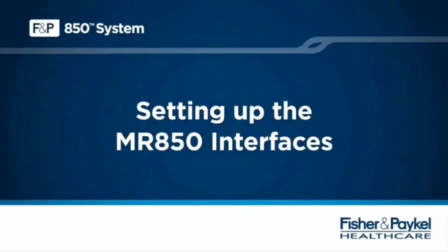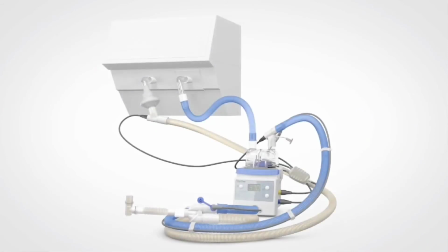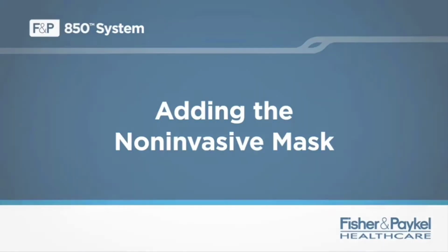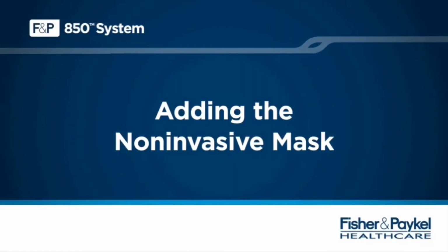The MR850 system is compatible with a wide range of patient interfaces. Fisher & Paykel Healthcare breathing circuits use standard ISO connectors and are compatible with common ventilators and patient interfaces, including closed suction, medication delivery, and monitoring devices. Next, let's look at adding a non-invasive mask to the dual limb breathing circuit.